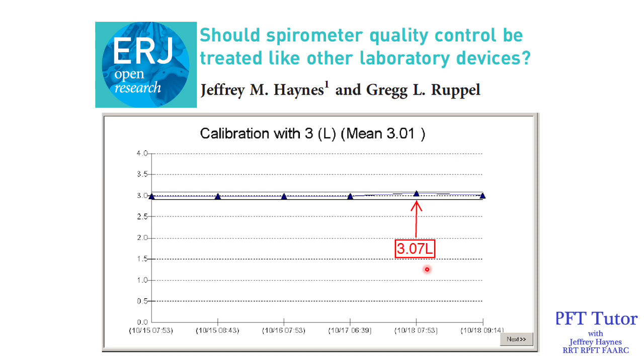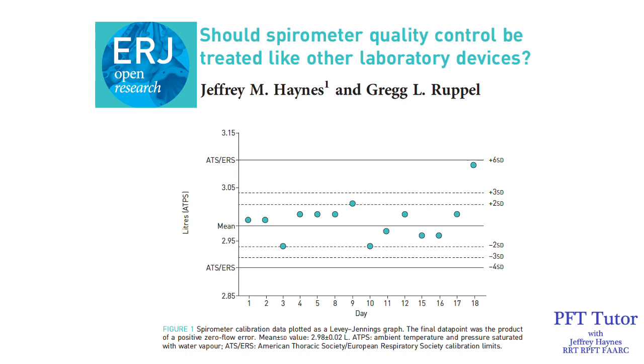However, this was a quite unusual finding for this particular device. I compared this reading of 3.07 to the historical performance of this spirometer, specifically looking at plus or minus 2 and 3 standard deviations. Even though it was within the ATS-ERS standards, it was almost 6 standard deviations outside of the historical control, and we had to recalibrate the machine. It's important not to fall into a false sense of security just because you're within the plus or minus 3% range. If things are trending up or down, or close to those limits, you may need to recalibrate your device.